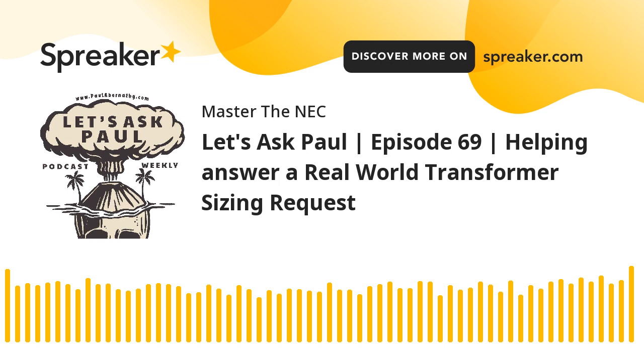Now, both of these are under 100 amps, so you're probably thinking, Paul, you're going to be using the 60-degree column. I am not. One is because I'm going to say that the terminals are rated 75 degrees or greater, and I'm going to say that the conductor's insulation, which is modern insulation, is THHN, THWN-2, XHHW-2. All of those are going to be 75 degrees or higher. So I don't really have a problem with that. 110.14(C)(1)(a) will tell me that as long as everything is rated, then it's fine. Okay, so I'm going to be using a 75-degree column.